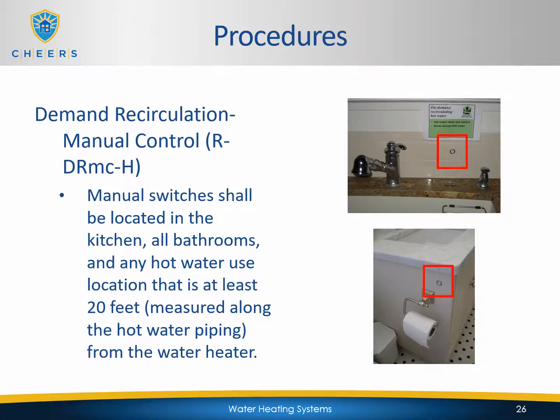So those manual switches or demand controls shall be located in the kitchen, all bathrooms, and any hot water use location that is at least 20 feet, and this is measured along the hot water piping from the water heater. So in the pictures here is just an example. This is a push button demand control. There are going to be different types. Oftentimes they are going to be some kind of push button control, because it's not a turn on and turn off. You just want something that's going to initiate the start of the pump. And so these are what you're going to be looking for in these various locations as part of your inspection.